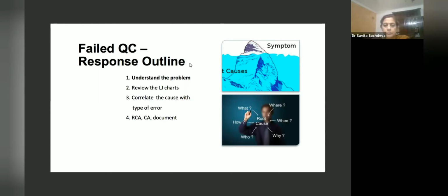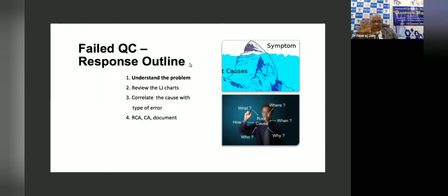Failed QC. We have to understand the problem. Yes, there is some problem. Then we have to review the Levey-Jennings chart, which we are preparing on the basis of this QC data. Then we have to see what is the type of error, whether it is a systematic error, which is affecting all our results, or a random error, where some error has happened suddenly. Whatever the situation, proper root cause analysis and corrective action is important. And again, whatever the situation, document, document, and document.